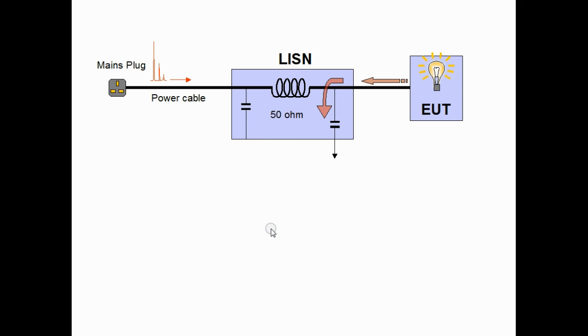One outstanding problem here is that we're connected to the mains and on the mains there is frequently quite energetic impulses coming through. Maybe the guy next door switched some lighting on or off and that can cause these impulsive disturbances which will be transmitted through the LISN and potentially down to our analyzer and damage the analyzer. The way we avoid this is to put in a transient limiter. This blocks the impulsive noise coming in from the mains but the downside is we have an insertion loss possibly up to 30 dBs, which means the signal here will be 30 dBs lower than the signal on the mains cable.